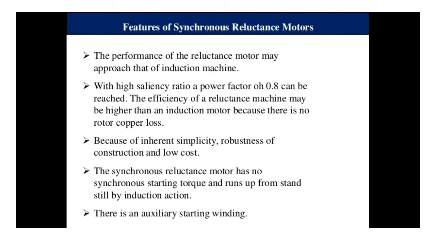Features of synchronous reluctance motors. The performance of the reluctance motor may approach that of an induction machine. With a high saliency ratio, a power factor of 0.8 can be reached. The efficiency of a reluctance machine may be higher than an induction motor because there is no rotor copper loss.